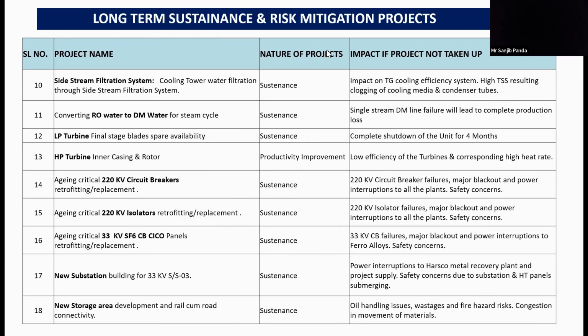Then converting RO water to DM water. Right now we have RO water of around 70 Nm³ per hour, and this we are circulating from the cooling tower. We are circulating back to the cooling tower. So this we are proposing to convert to DM water.